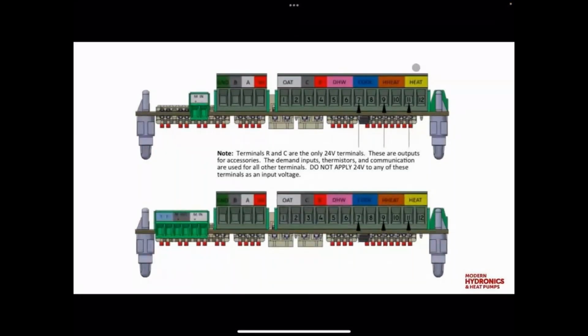The difference here is that the heat call looks at outdoor reset temperature, and the high heat call is just a fixed set point temperature, which you select. Most of the time, the heat call would be used for things like radiant floor heat, and the high heat call would generally be used for things like fan coils, air handlers, or baseboard radiators. But these are just dry contacts. We're just looking to make dry contact across either the two heat terminals or the high heat, and it'll put the system in that mode.